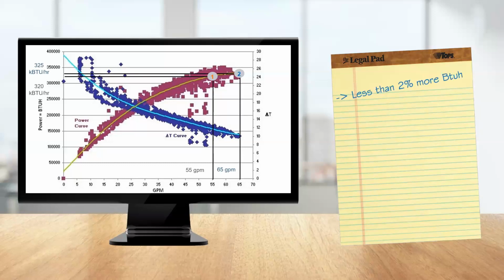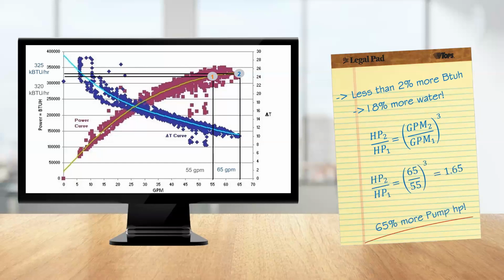So if we look at that, there is less than 2% more BTUs, and we're utilizing 18% more water. If we put this into our pump affinity law, the horsepower requirements increase by the cube of the increase in flow. Between point one and point two, there is a 65% increase in pumping cost to achieve a 1.6% increase in cooling. It's not very efficient.